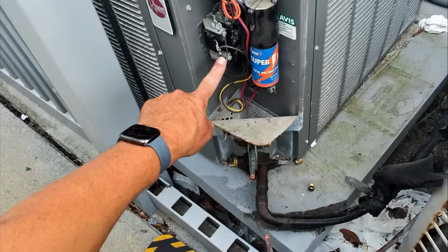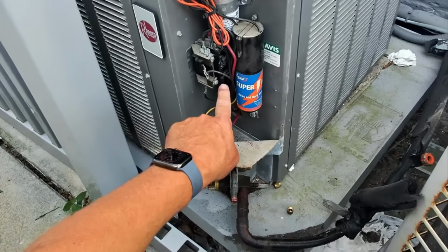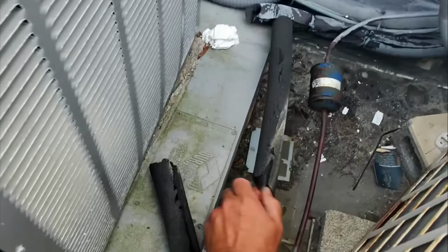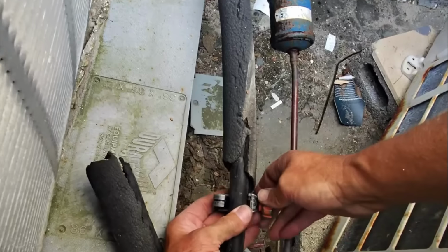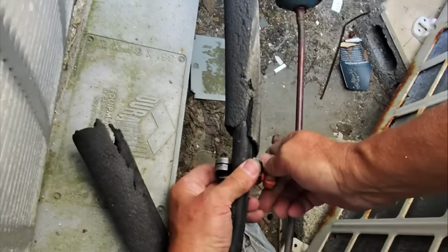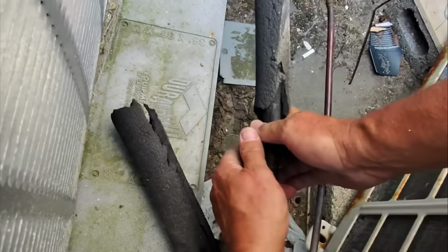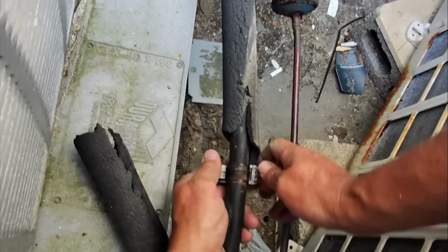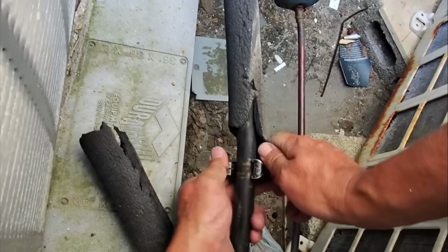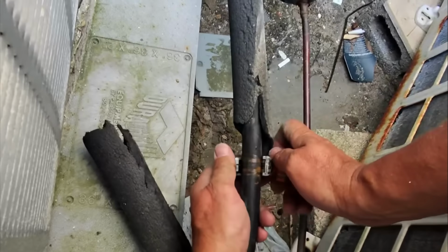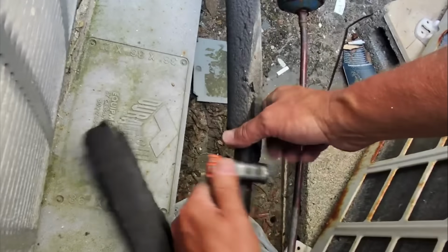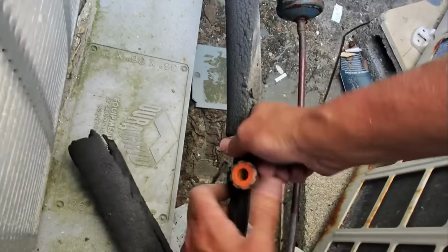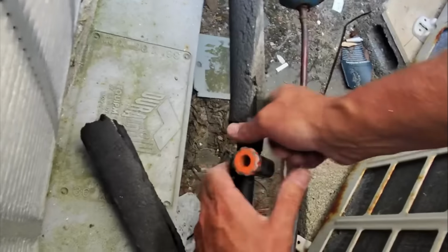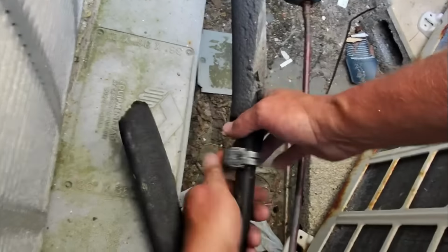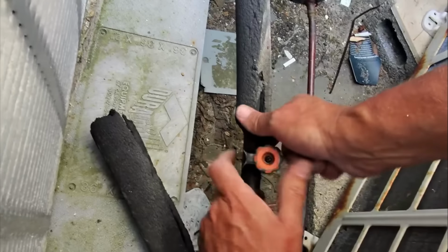All right, I disconnected the whip from the bottom of the contactor, L1, L2, and cut my ground out. That's out of the way. Cut my 3/8, now I'm going to cut the 7/8. This little Mavic tubing cutter has been giving me problems lately, also probably because this 7/8 is slightly out of round, but we'll get this cut. Then we're going to figure out how we're going to manipulate the piping to accommodate this new outdoor condensing unit, which is side discharge, but we'll be all right. Let's just get this unit out of the way first.